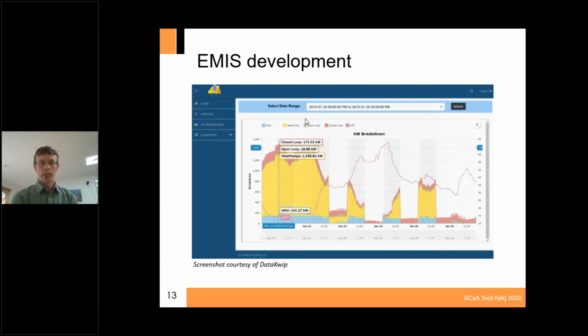When you get the tools developed - this is a snapshot from DataKwip, an East Coast company near DC that we're using on one of our projects. They're doing virtual power monitoring. Even though the building didn't have VFDs and point-of-use meters all over the place, they were able to take nameplate data of equipment, calculate the kW usage, and start plotting that.